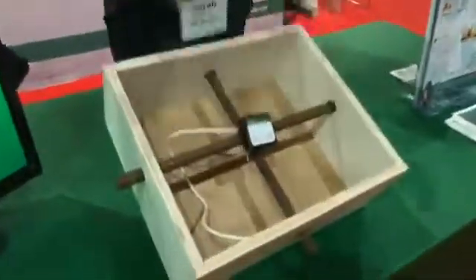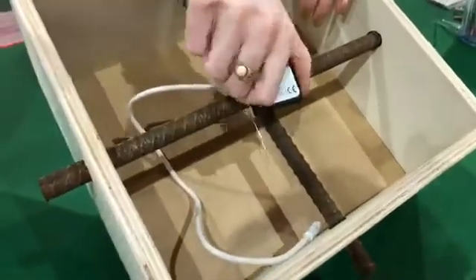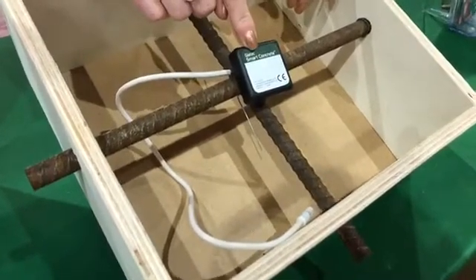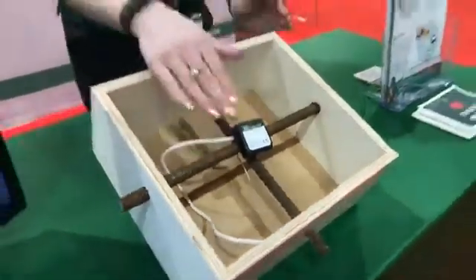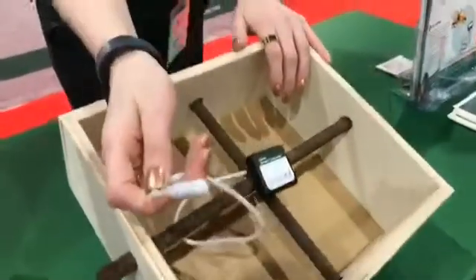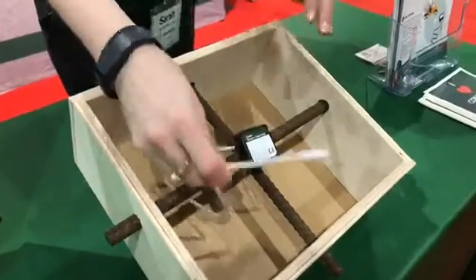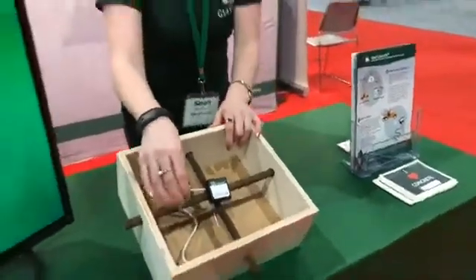Let me show you a little bit about how these Smart Concrete Sensors work. Because Giatec has made the solution wireless, we've been able to do a lot more on the data acquisition side. Down here is what I have for the maturity logger. This part right here — the black rock, as we call it — is the Bluetooth transmitter, the data logger, and the reader. Everything that requires any computer activity is in this little rock. Once you pour the concrete, this temperature cable needs to be installed where you want to receive your point. These can extend anywhere from the very surface up to 10 feet or 3 meters deep.